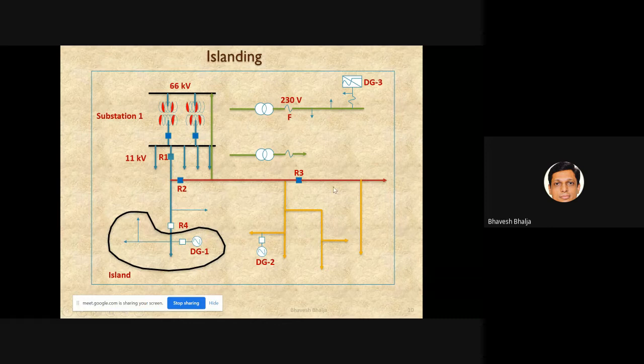Another lateral I have connected another DG, and you can see if I open this R4 isolation device, if something goes wrong somewhere here and R4 is open circuited, then there is formation of an island - shown by the black thick line. So there is formation of an island, and whatever loads are here are supplied by this DG1 depending upon its capacity. So this is also another example of islanding.